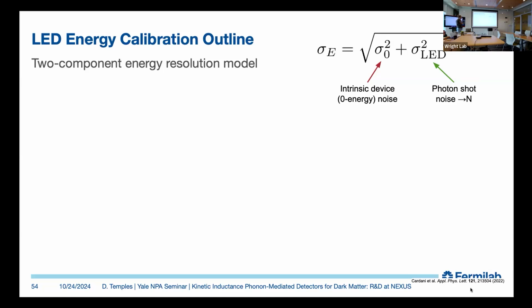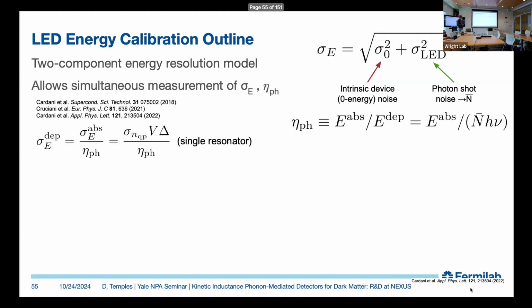The width of that peak is set by 2 components. One is the intrinsic device noise, the sensor noise. This is the 0 energy resolution, if you will. As well as a contribution from the photon shot noise, which is proportional to the average number of photons that are delivered with each pulse. Without going too much into the details, this allows us to measure both the energy resolution and the phonon collection efficiency at the same time. Both the energy resolution as deposited in the substrate and the resolution on energy absorbed by our sensor.